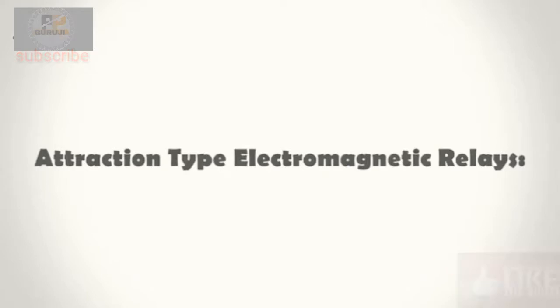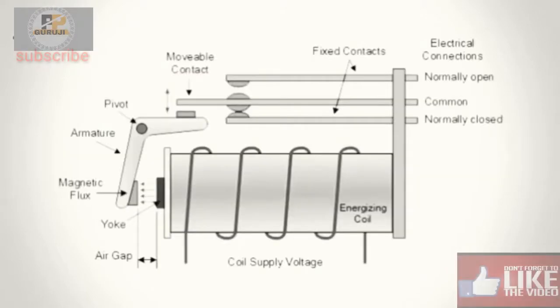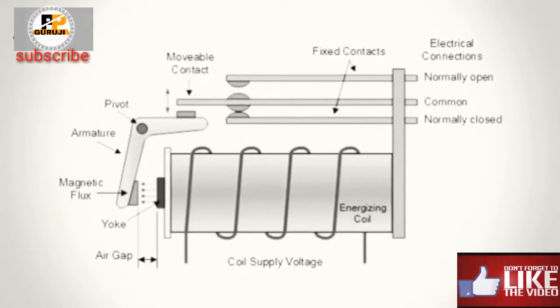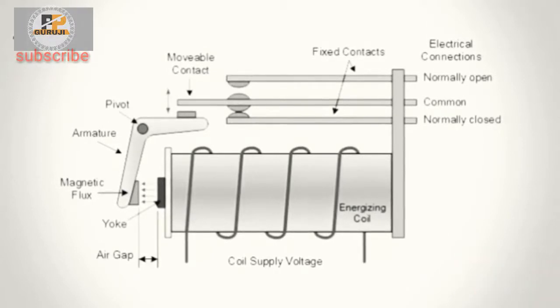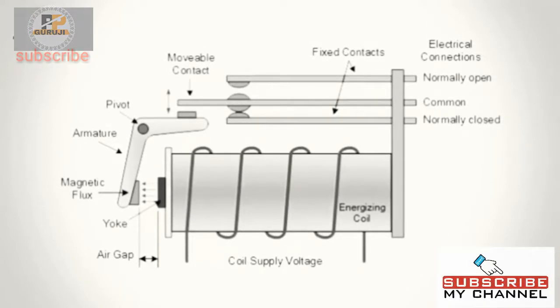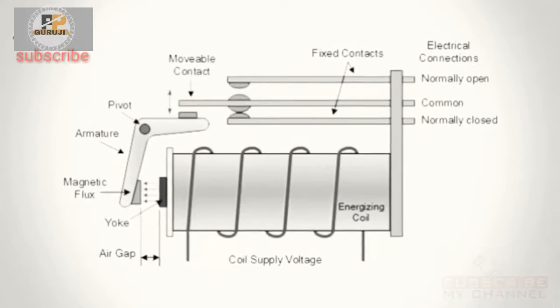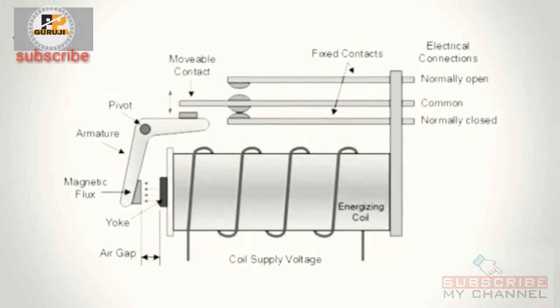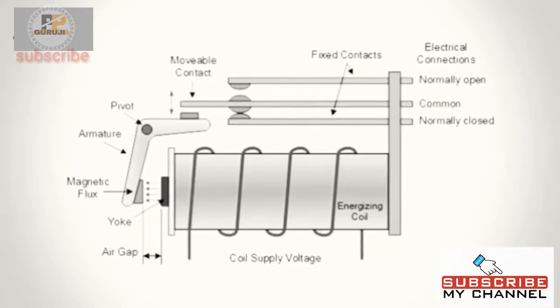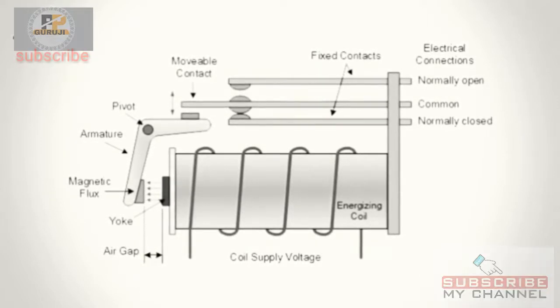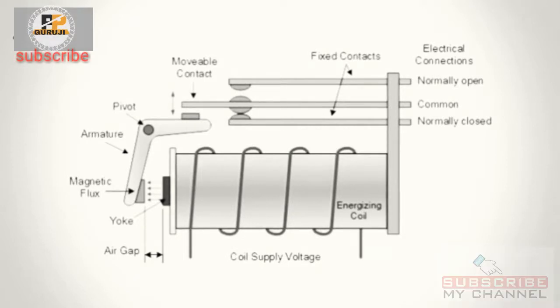Attraction type electromagnetic relays. These relays can work with both AC and DC supply and attract a metal bar or a piece of metal when power is supplied to the coil. This can be a plunger being drawn towards the solenoid or an armature being attracted towards the poles of an electromagnet as shown in the figure. These relays don't have any time delays, so they are used for instantaneous operation.